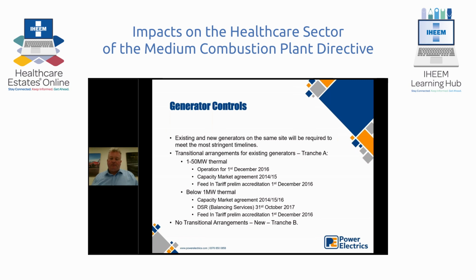There are some criteria you have to meet. If you have a capacity market site or have been running a demand side response contract from before 2016, then you may be okay. But the legislation has changed slightly, and it's now the responsibility of the operator with the aggregator to make sure everything is abated. So effectively everything becomes what's known as tranche B, meaning anything from 2019 onwards needs to comply with the Medium Combustion Plant Directive.